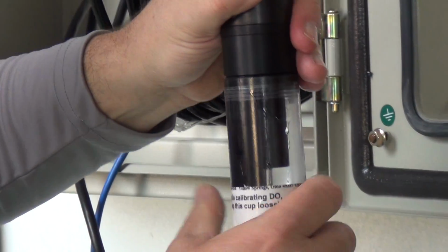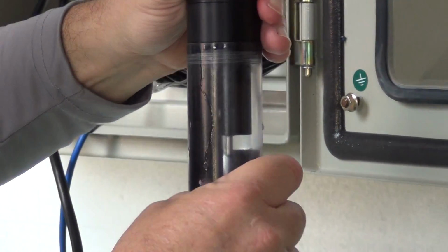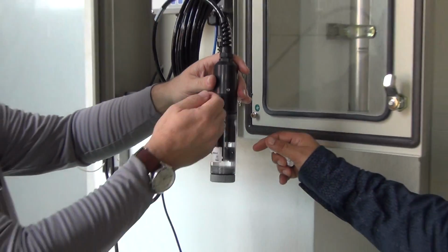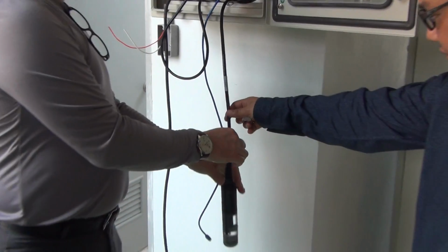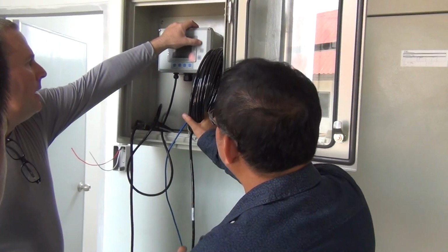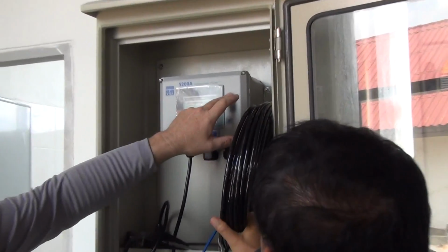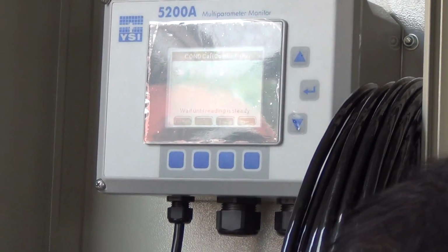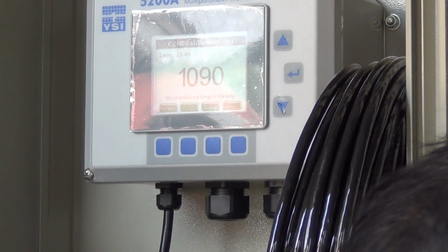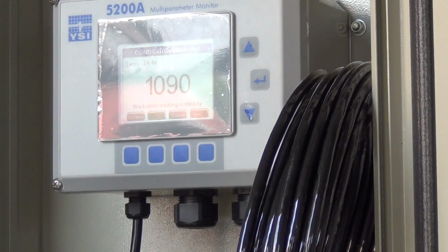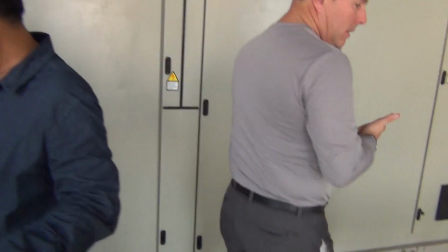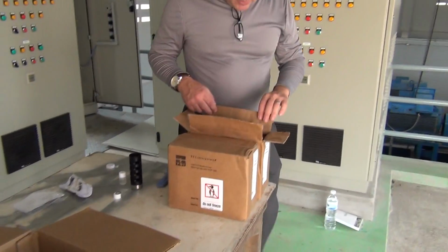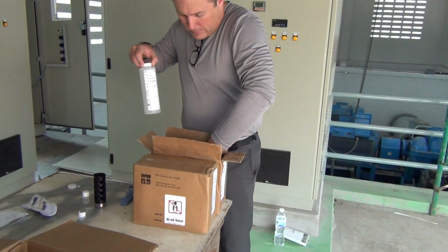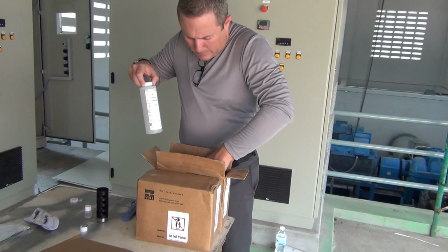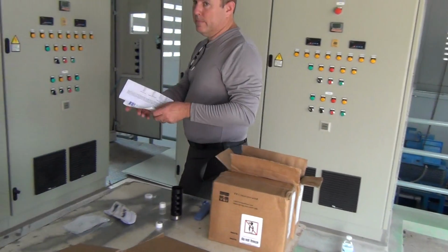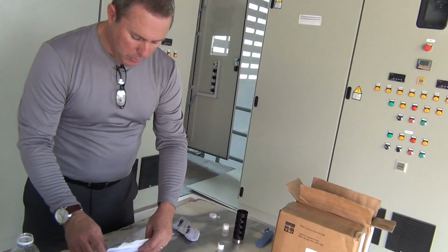All right. So this is 1,000 microsiemens conductivity solution. I have tightened it tight this time. I'm now going to take the probe, hang it down. I'm going to go to our menu and select conductivity. I'm going to press the enter key and I wait. I do not have to do anything while it does that, except I'm going to go over here, and normally in the box is a paper, and on the paper is a temperature chart. This is very important.